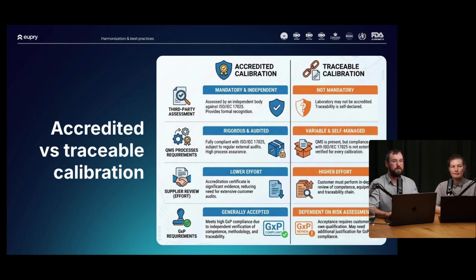With a traceable calibration, you will have to trust that calibration laboratory's practices and how they manage their quality. Second is that the QMS processes are really rigorously defined in ISO 17025, just like with any other quality standard. Whereas traceable calibration can be performed, I say can, because it can be performed without a QMS or quality processes in place. It doesn't necessarily have to be, but it's just something to be aware of.